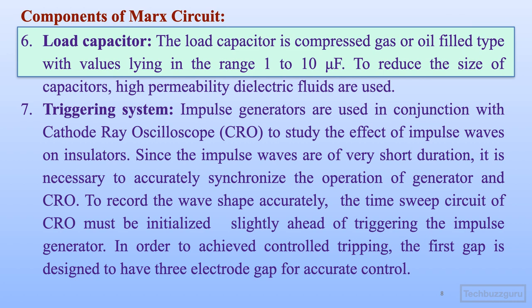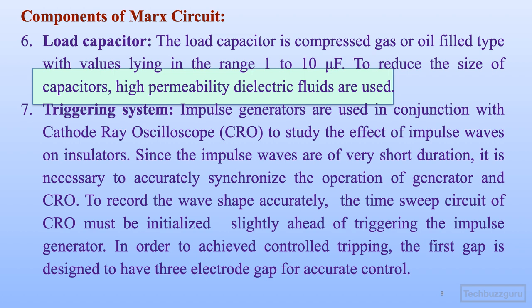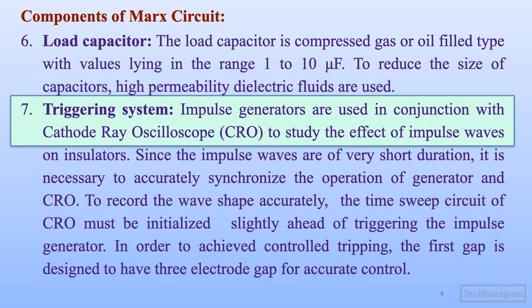The sixth element is the load capacitor or the test object. The load capacitor can be a compressed gas or oil filled type with values lying in the range of 1 to 10 microfarads. The size of these load capacitors can be reduced by using high permeability dielectric fluids. Lastly, the triggering system is used for synchronizing the operation of the impulse generator with the cathode ray oscilloscope. Generally all impulse testing is done and observed with the help of a CRO for accuracy.